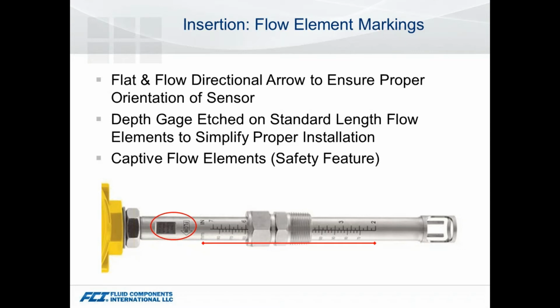And then finally, a feature that's very unique to FCI is captive flow elements. If you look at the sensor itself, you see that flared edge at the end of the extension prior to the sensor. That flared edge is captured by the compression fitting packing gland, even a thread-on flange, to the point that if you're in a higher pressure system, you don't have to worry about that flow element coming completely free of the compression fitting once you've loosened it to remove for preventative maintenance.